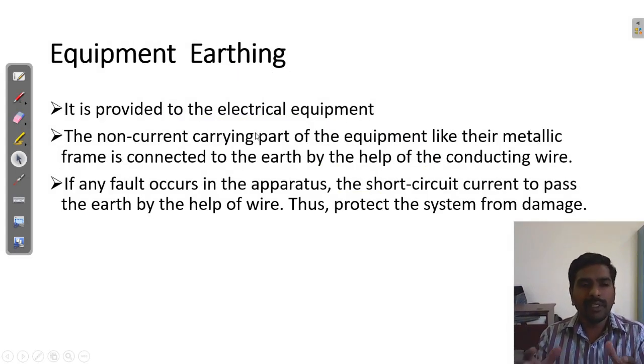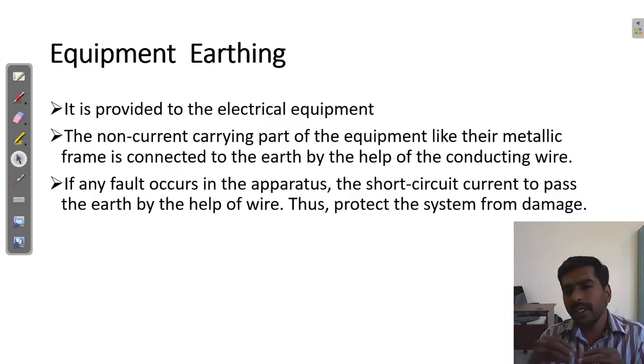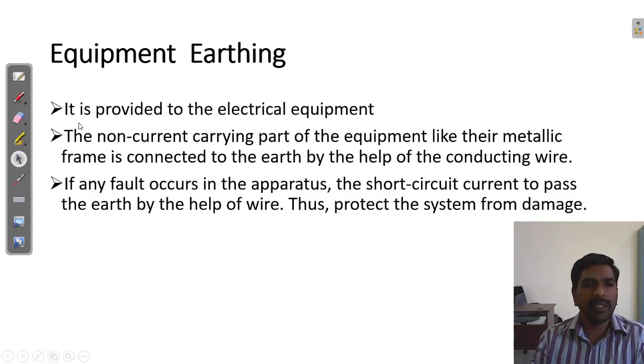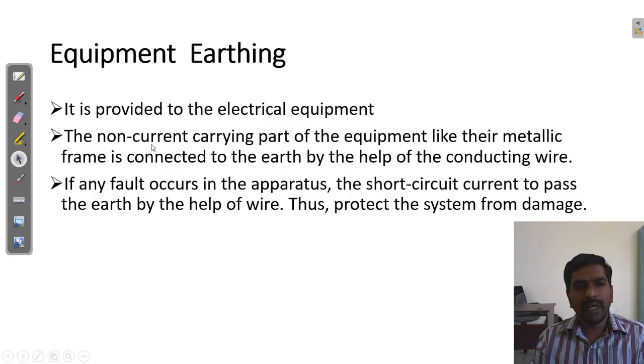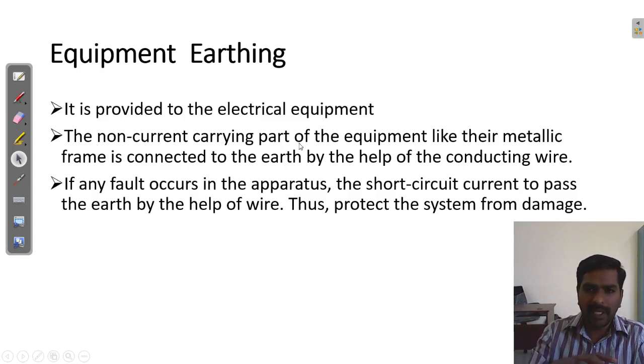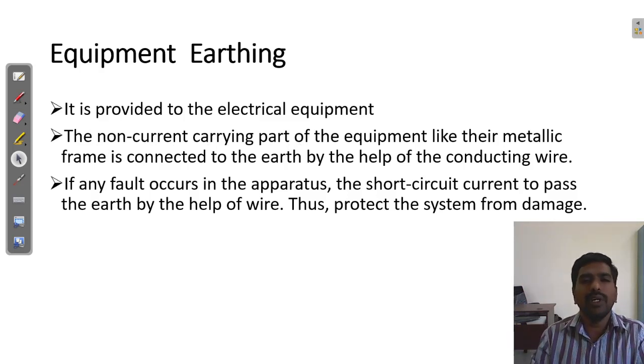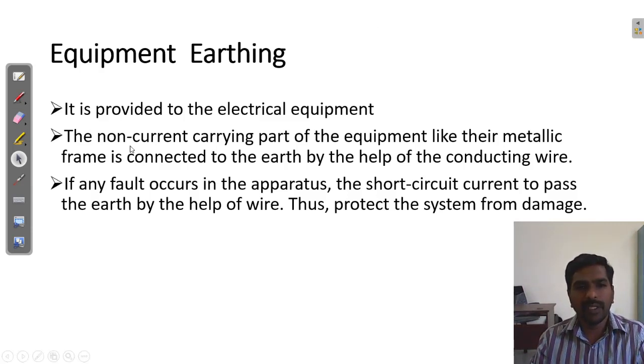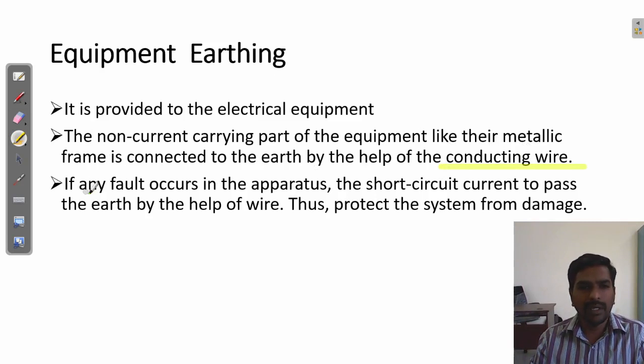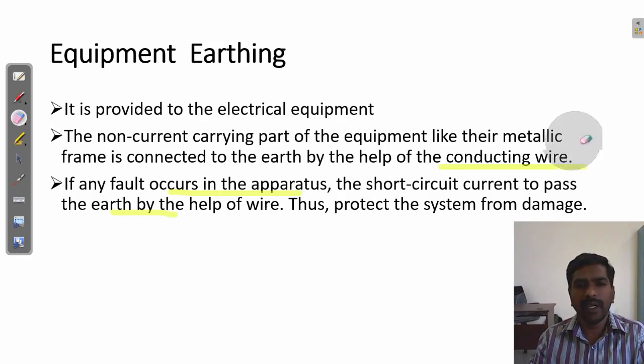Equipment earthing means all appliances and equipment are connected to earthing — that is called equipment earthing. It is provided to electrical equipment. The non-current carrying part — that is the equipment body — there may be a metallic body or frames. Those frames are connected through earthing wire. The non-current carrying part of the equipment like the metallic frame is connected to Earth with the help of conducting wire. If any fault occurs in the equipment, the short circuit current goes through the Earth with the help of the wire. This is called equipment earthing.